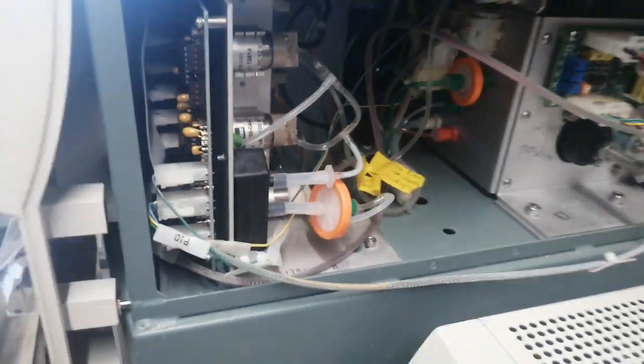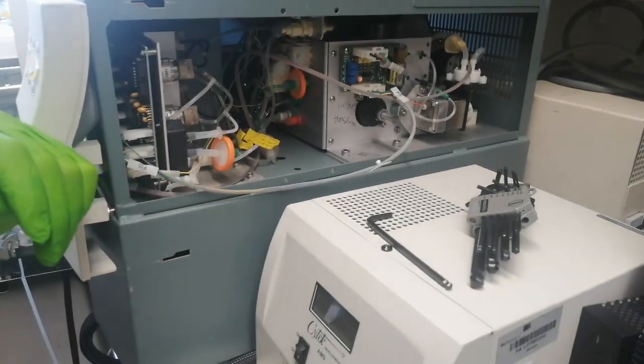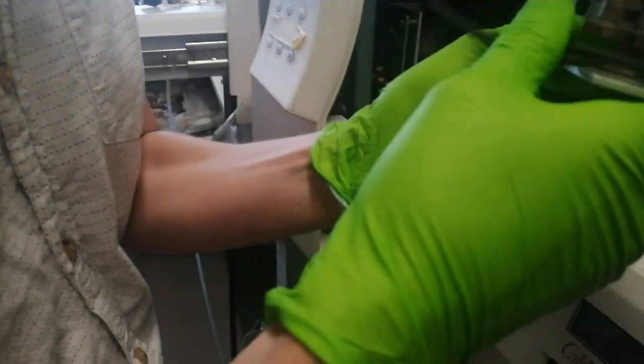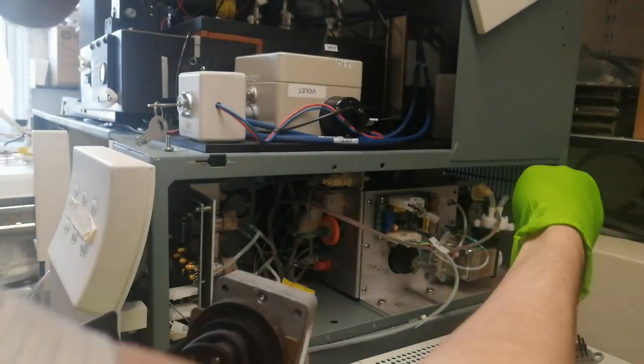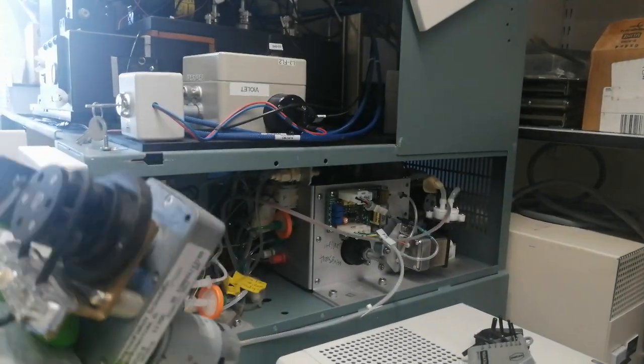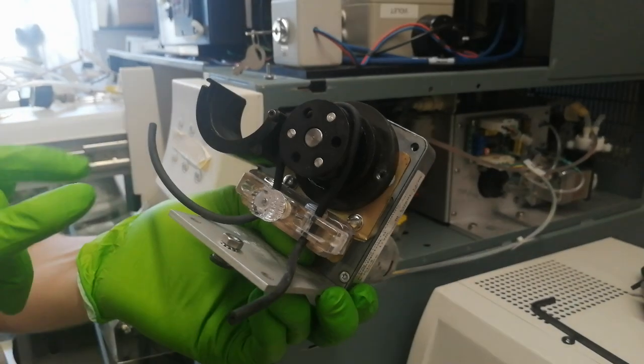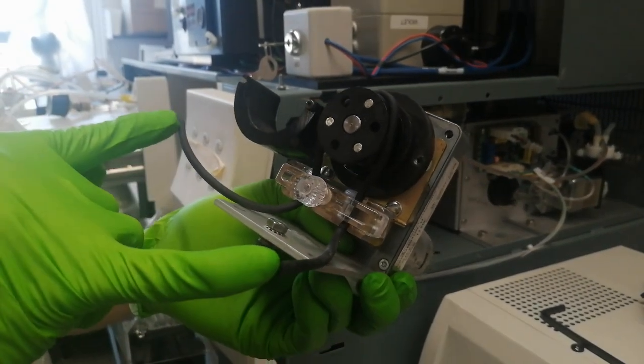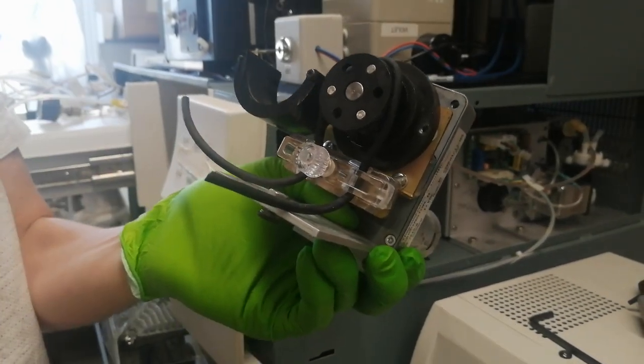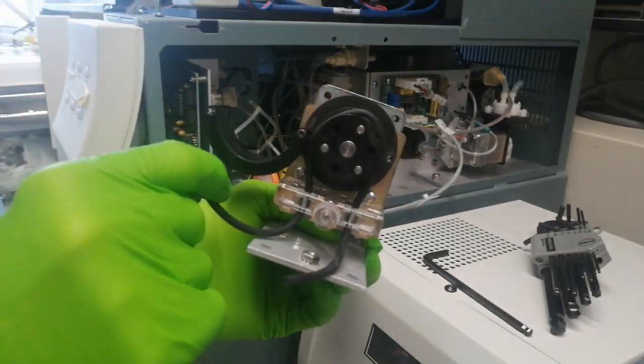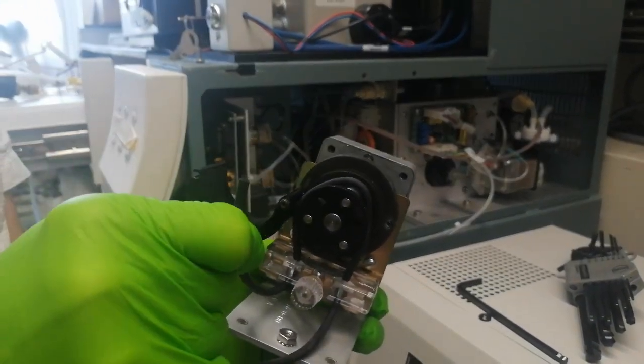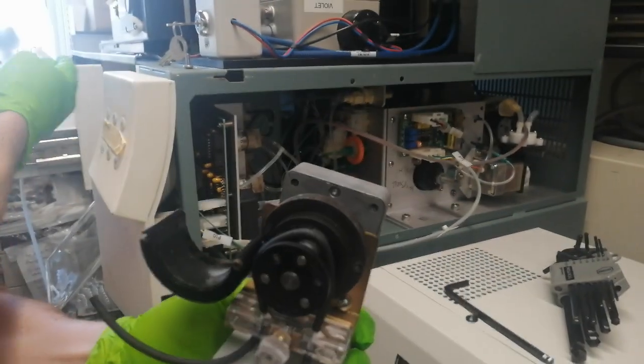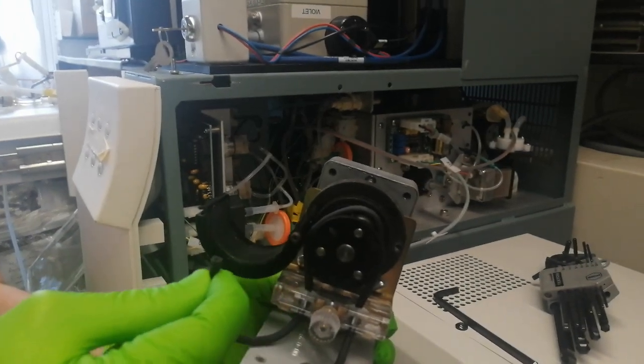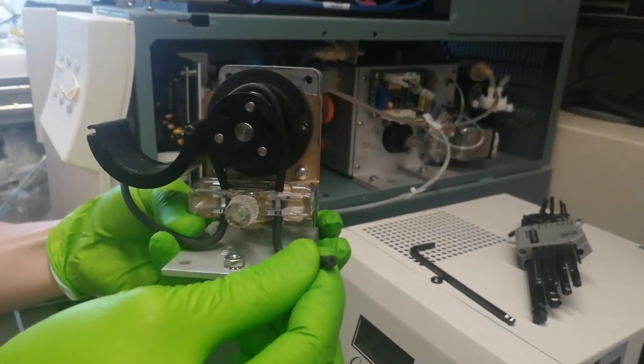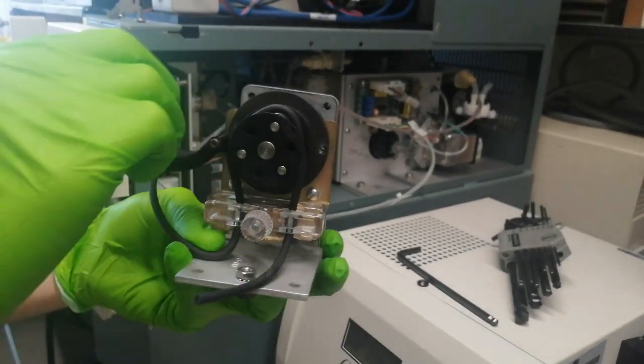The other thing which I have already changed, which was part of the pump, I'll show you on this one. So this is the peristaltic pump. This is the one I've just replaced, and it sits back here. So you have this peristaltic pump tubing. It has two connectors going to each end of it. The one on this side is a straight through connector, and it goes from another piece of black tubing exactly the same, and that goes to the back of the flow cell eventually, but it connects to a long piece of the same sort of tubing. On the other side there's a T-shaped connector which goes to some orange waste line tubing. So what you do is when you come to it, that will be closed and that will be in place.